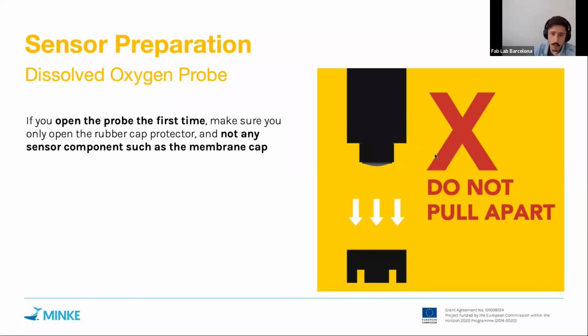Now, probably the most difficult one that I mentioned earlier, let's go with it. It's the dissolved oxygen probe. Whenever you open it for the first time, you will see that it has a protective cap, basically a rubber cover that protects the tip of the sensor. But you will also see that it has a small Teflon membrane that is not to be removed when you open that protective cap. So whenever you open it for the first time, be very careful and do not pull apart this part as shown in the picture, but only remove the protective cap. That is very obvious, but sometimes if you pull hard or too fast, the membrane cap will come along with the protection.